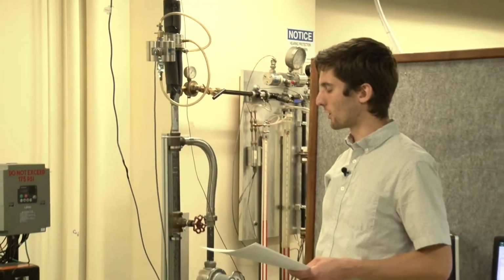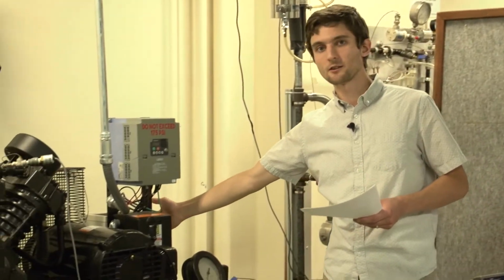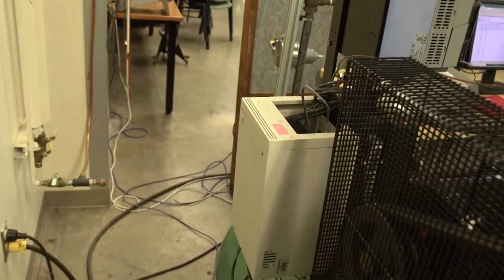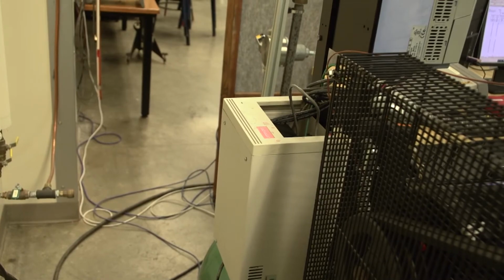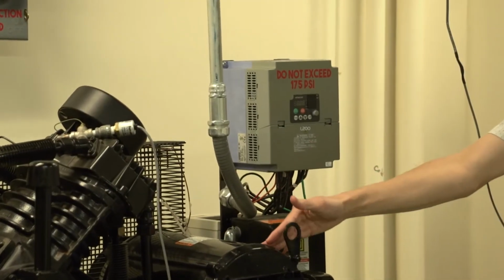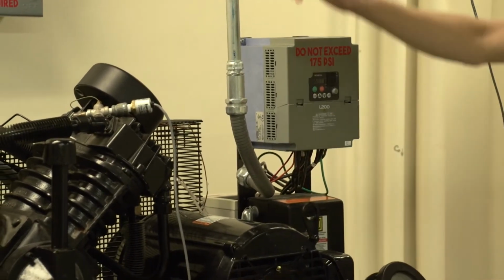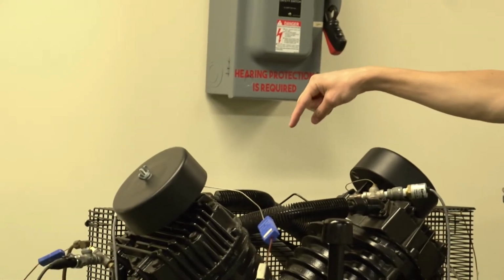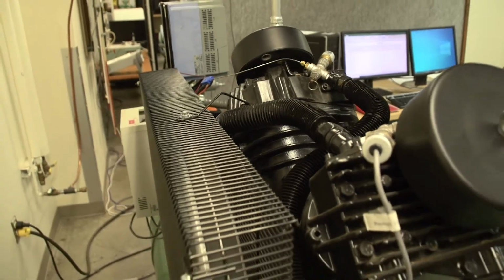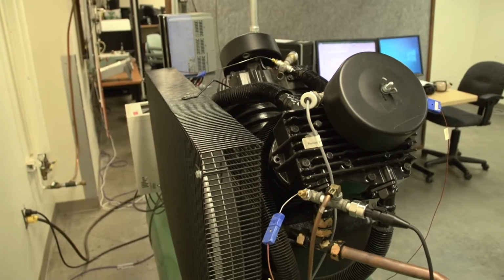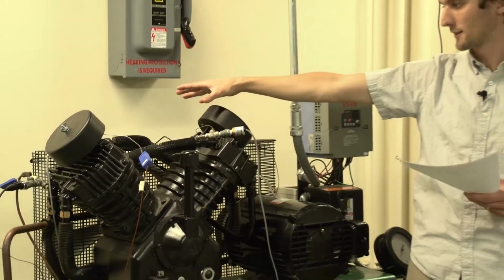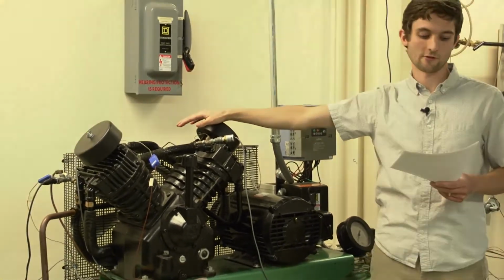We also have 1 power cell back here. It's enclosed because it's measuring 3-phase power. This measures the power input to the motor. And there's a magnetic pickup on the back here which measures the rotational velocity of the flywheel for the compressor.